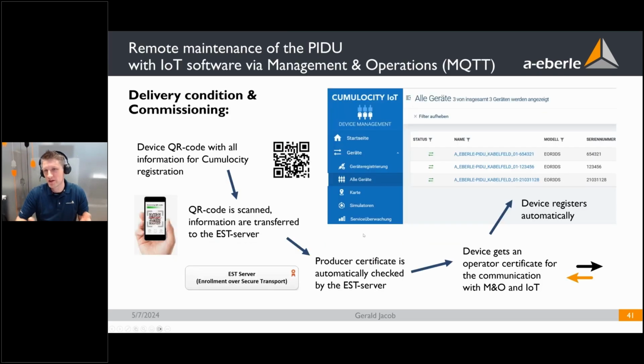Here's some further information, because we are talking about thousands of devices, not only short circuit indicators. There are also other devices in the digital secondary substation that shall be implemented in this central IoT software. And here you can see the onboarding process. On each device in the secondary substation, there's a QR code that can be scanned with an app, for example. And this information is transferred to the central certificate center.